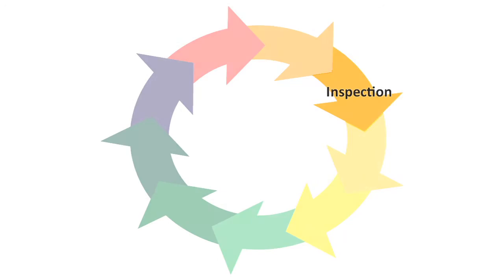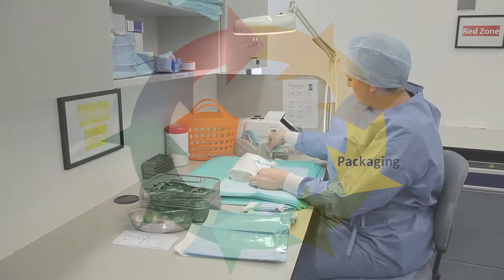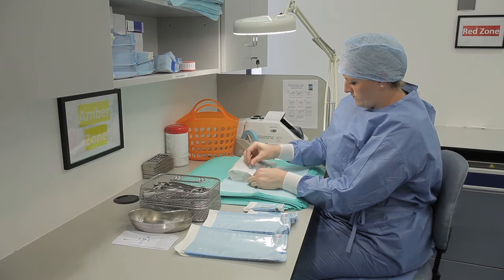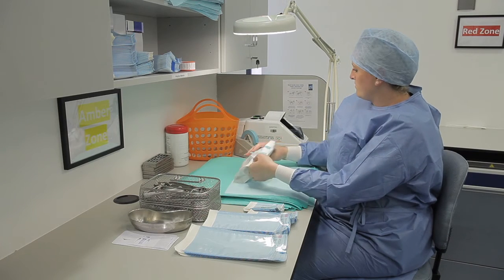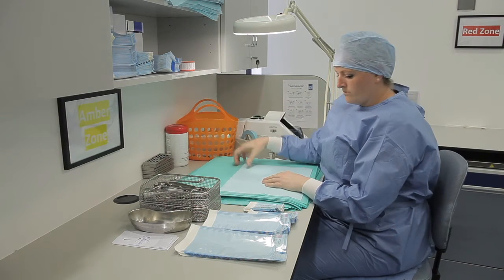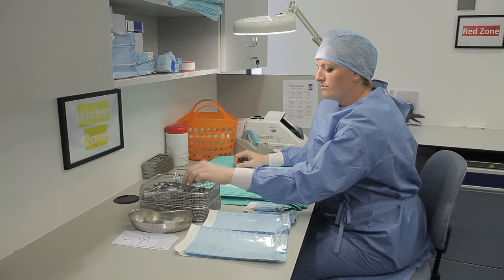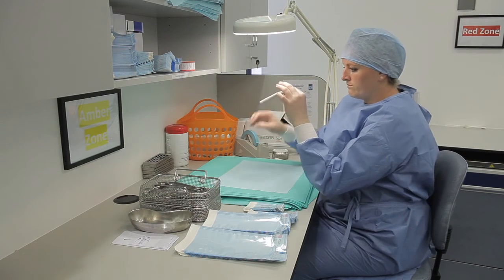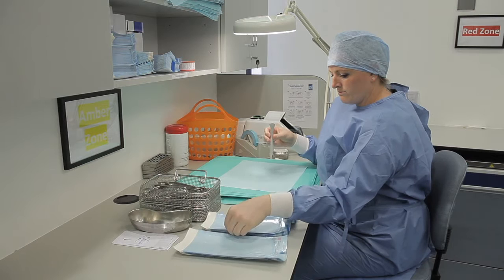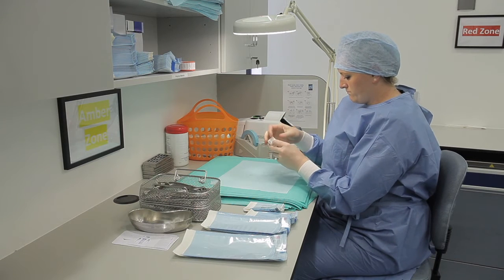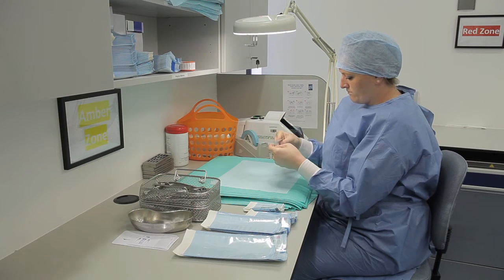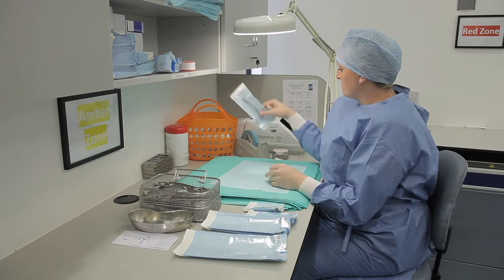We are now ready to move on to Step 4, Inspection, and Step 5, Packaging. All RIMD must be inspected prior to packaging. Ensure that there is adequate lighting in the inspection and packaging area. Check that the inside of lumened RIMD, such as high-volume suction tips, are clear. Inspect all other RIMD for debris, rusting, breakage, and hinge fractures.